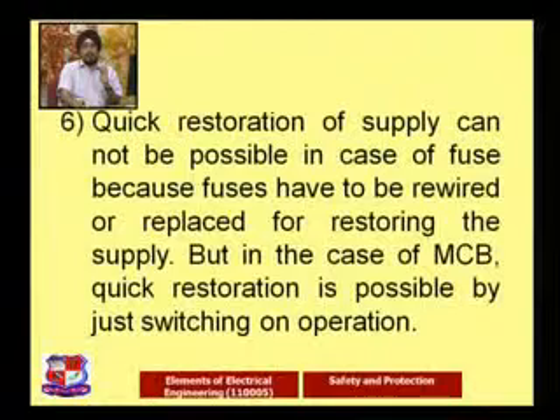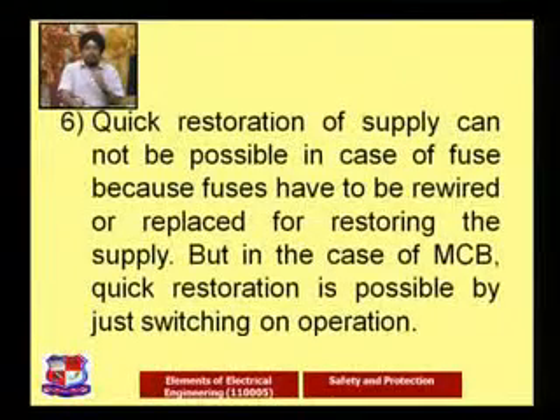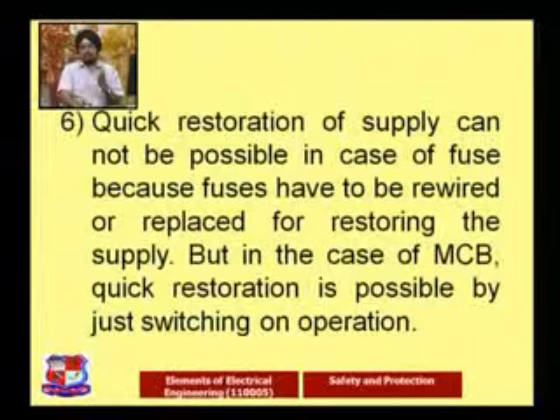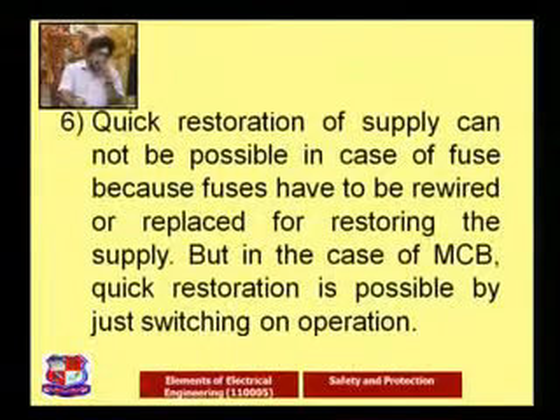The major advantage of the MCB is quick restoration of the supply, which is not possible in the case of a fuse. With the fuse we cannot make a quick restoration. We have to take out the fuse, check it, rewire it, replace it, and then the supply is restored. But in the case of the MCB we just have to switch on that particular faulty zone and see whether the fault is clear, and if it is okay, it will turn on that particular circuit or zone. So quick restoration is the biggest advantage of the MCB. Time is saved.